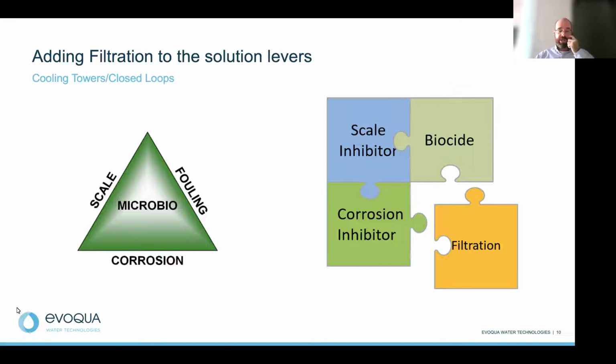And so Mike is going to talk about this a little bit later in more detail, but just on a high level, if you think about all the sand and silt that may be in a tower basin, for example, when you're adding those scale and corrosion inhibitors, the corrosion inhibitor can't lay that nice protective film on the metal to prevent the corrosion cell. You add in those biocides, oxidizing, non-oxidizing. Again, it cannot penetrate all that sand, silt, and debris. And so the bacteria has a great, nice habitat to grow with nutrients and proliferate. Filtration is absolutely the missing puzzle piece, in my opinion, for you running a really, really good program.